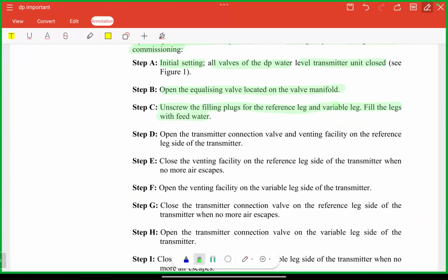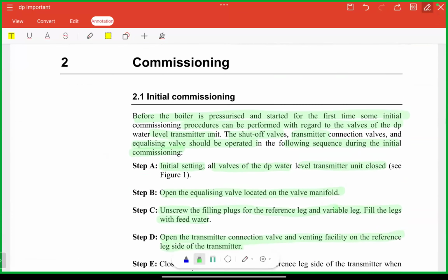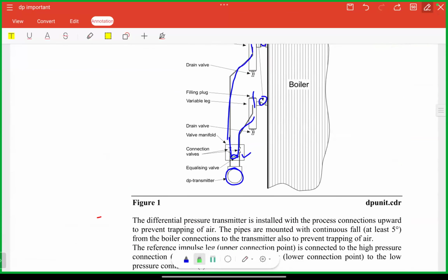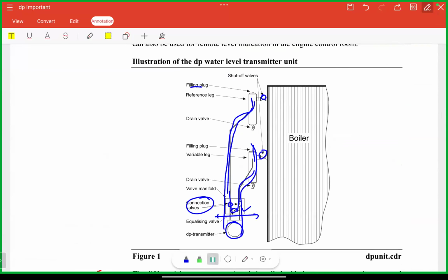Then open the transmitter connection valve and venting facility on the reference leg side of the transmitter. Open the connection valve. Where is the connection valve? These are the connection valves. Open this connection valve. Now water is going to be available all the way to the DP transmitter, but the pressure is going to be equalized because your equalizing line is open.